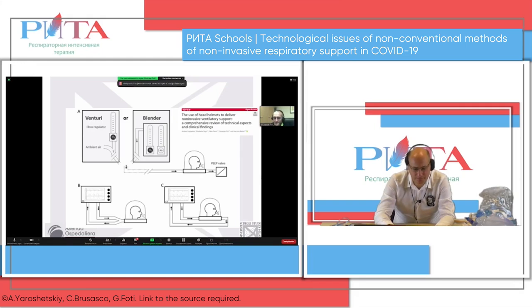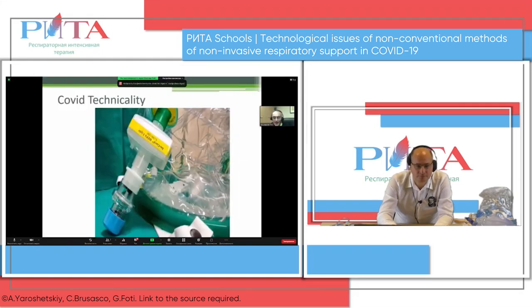Now I'm going to show you why. This is a typical setup for a COVID patient, right? The helmet, the HEPA filter, the PEEP valve. If you put the HEPA filter - which also acts as an HME and reduces the noise - here, it adds resistance.